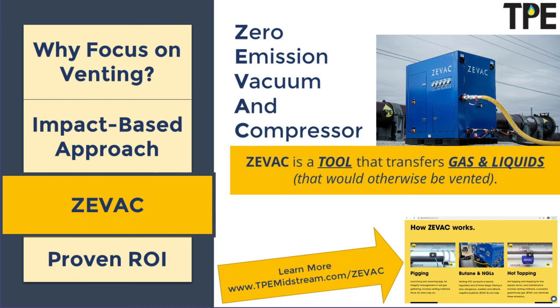You can learn a lot more about the equipment itself on our website. I don't want to spend this valuable time going too deep into the equipment, but we regularly do distribution applications, which are 55 PSI and lower, all the way up to storage applications at 2200 PSI. So there's a huge pressure range that we're capable of dealing with. We can take it all the way to 0.0 PSI in select applications.